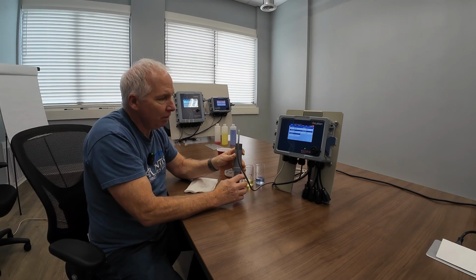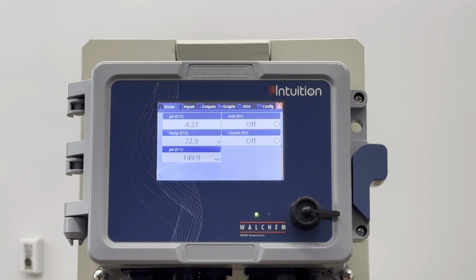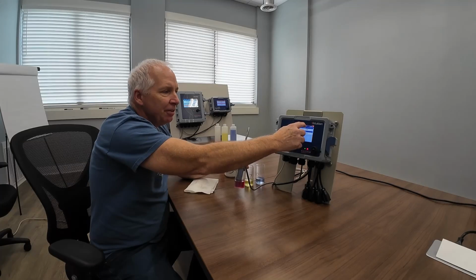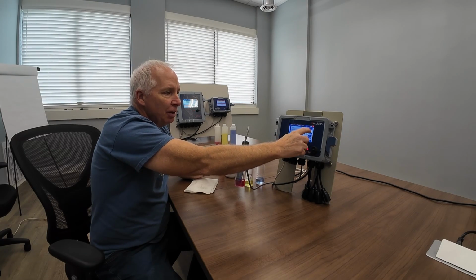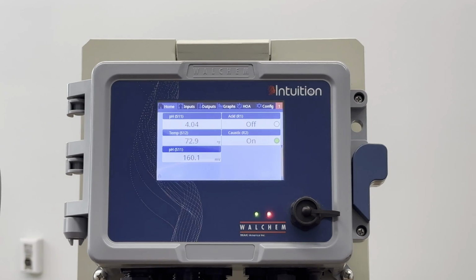Go to pH buffer 4. Stir it around a little bit. Wait and see where this stabilizes. Seems to be bouncing around 4.04, 4.05. I'm happy with that. If I now go back into my HOAs, I can turn on the 2 relays. You'll see the caustic's feeding right now because we're around 4. I'm going to put it back into my process.